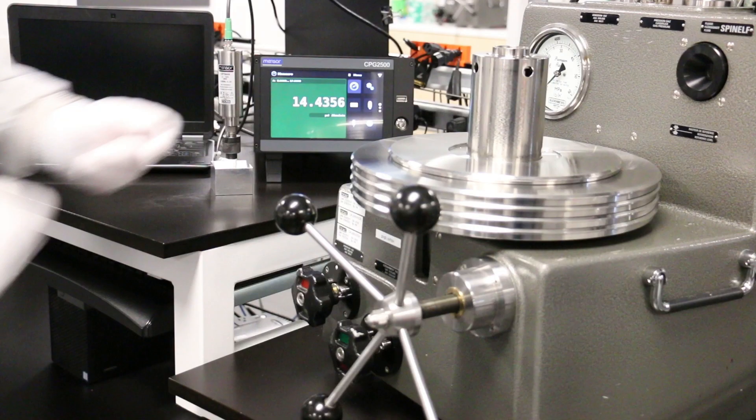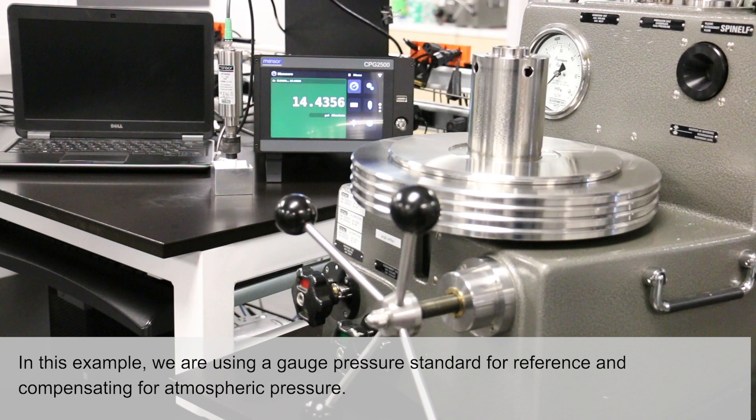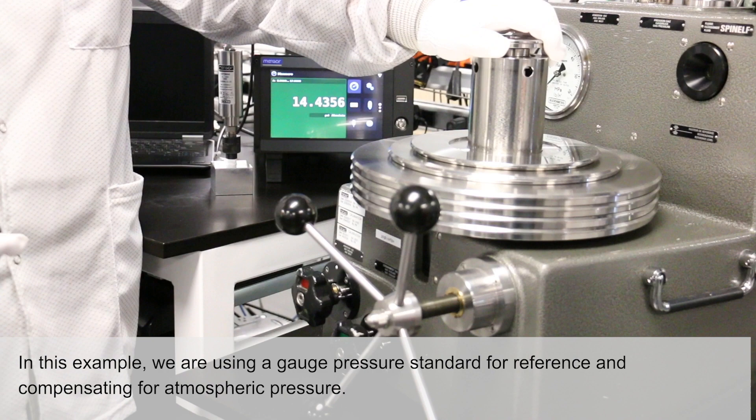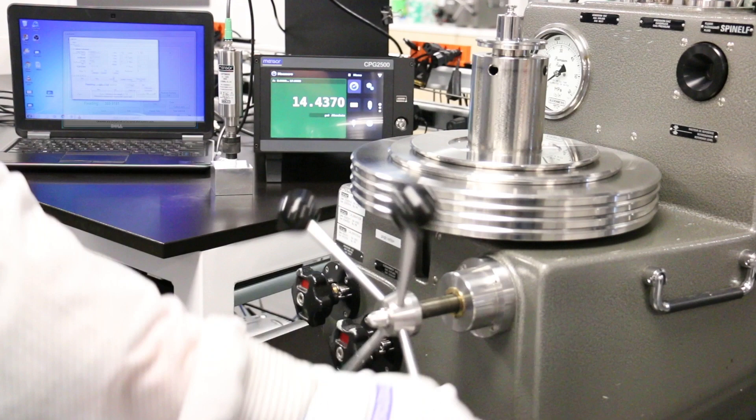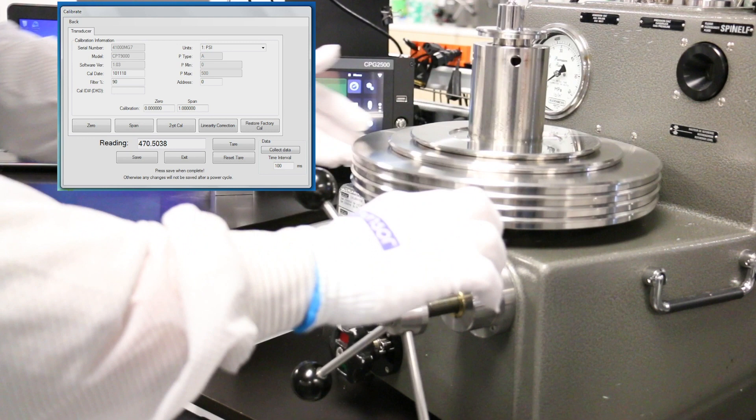For this example, load the weights that will create a pressure close to 500 PSIA. Best practice prescribes that the transducer be exercised by running it from the minimum range to full scale at least two times, dwelling at each extreme for two to three minutes.